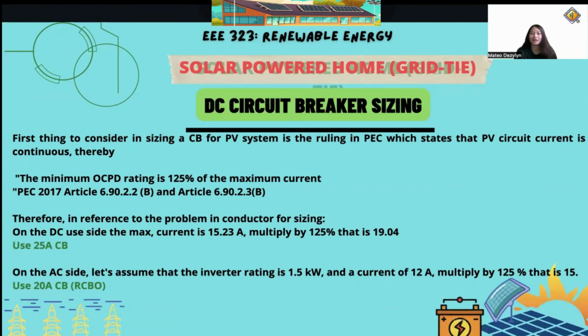First thing to consider in sizing a CB for PV system is the ruling in PEC which states that PV circuit current is continuous. Thereby, the minimum OCPD rating is 125% of the maximum current. PEC 2017 Article 6.90.2.2b and Article 6.90.2.3b. Therefore, in reference to the problem in conductor sizing, on the DC side, the max current is 15.23 ampere multiplied by 125%, that is 19.04. Use 25A CB. On the AC side, let's assume that the inverter rating is 1.5 kilowatts and a current of 12 ampere. Multiply by 125%, that is 15. Use 20A CB or RCBO.